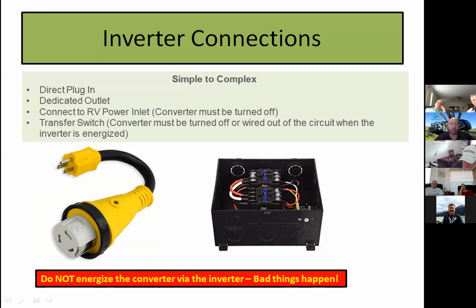Another way is to have a dedicated outlet - run wiring from your inverter through a junction box to a duplex outlet. That way the wire is up and out of the way, stapled or run correctly. That outlet becomes dedicated specifically to run off your inverter - works well for something like a television inside a bedroom.